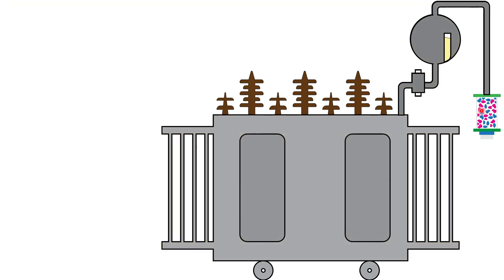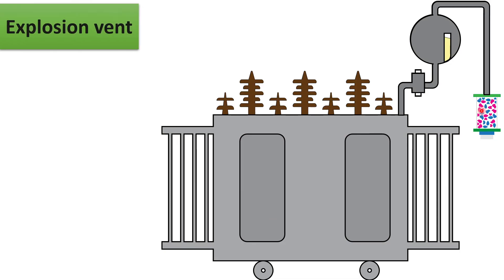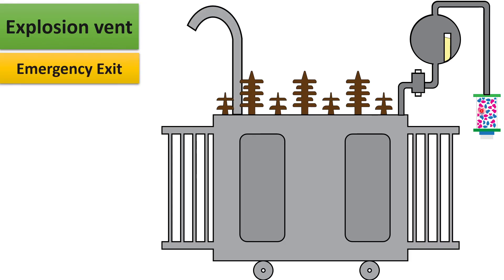The next important protective component is the explosion vent, provided on the top of the transformer, positioned slightly higher than the conservator tank. The purpose of this explosion vent is to provide an emergency exit for oil or gases in the transformer. In case of any fault condition, sudden pressure is created due to released gases or expansion of oil. To release that pressure, the explosion vent is provided. When too much pressure is created, the diaphragm inside the explosion vent ruptures, and oil and gas can be released through it, protecting the transformer from further damage.